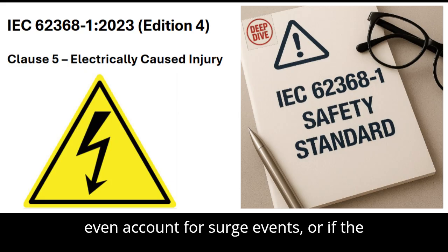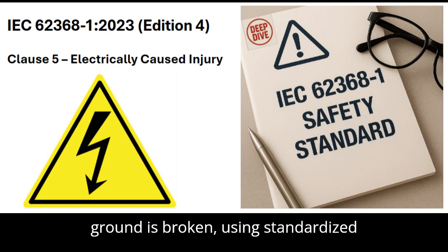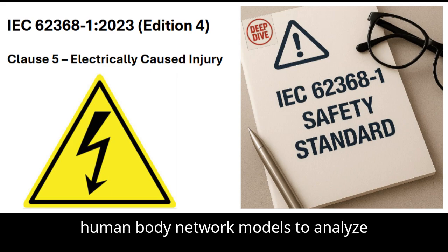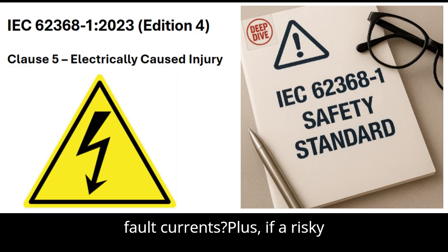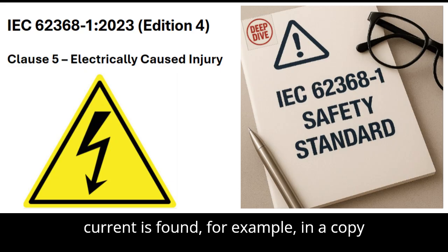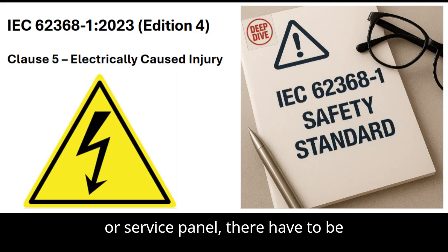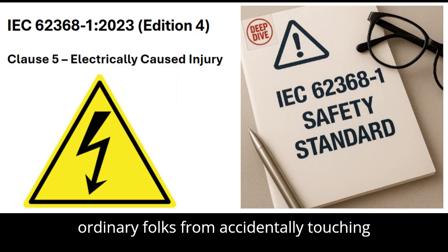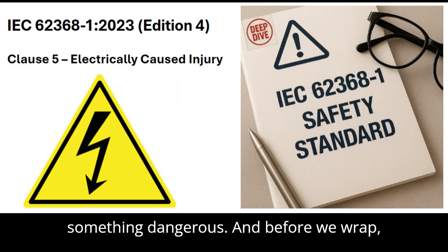Did you know those tests even account for surge events or, if the ground is broken, using standardized human body network models to analyze fault currents? Plus, if a risky current is found, for example, in a copier service panel, there have to be interlocks or instructions to prevent ordinary folks from accidentally touching something dangerous.